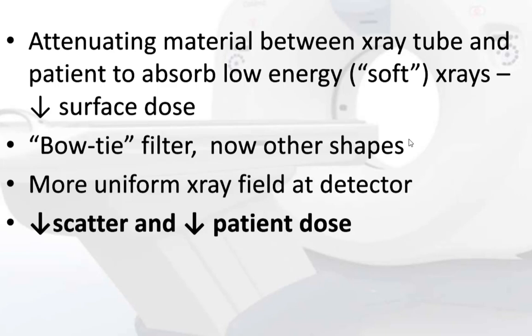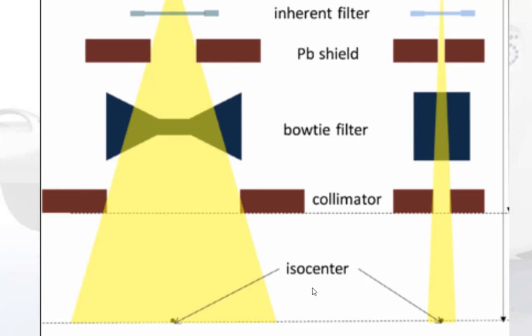Filter is another important concept when discussing CT dose. It is attenuating material between the X-ray tube and patient to absorb low energy or soft X-rays, and it decreases surface dose. There are different shapes of filters — one of the most common is called the bowtie filter. It creates a more uniform X-ray field at the detector, decreases scatter, and decreases patient dose.